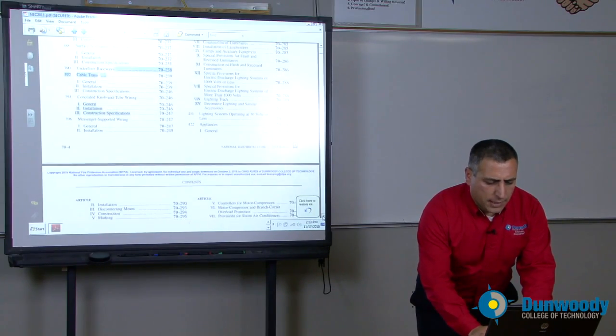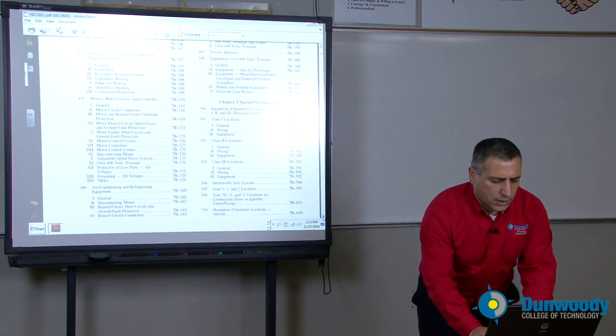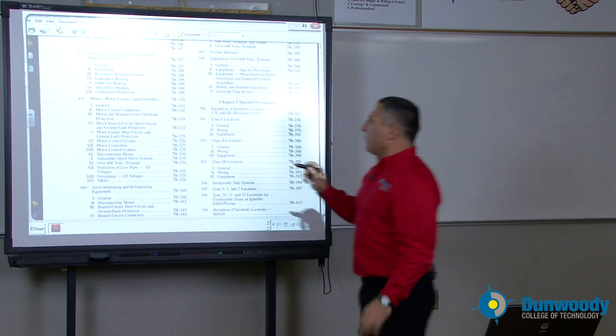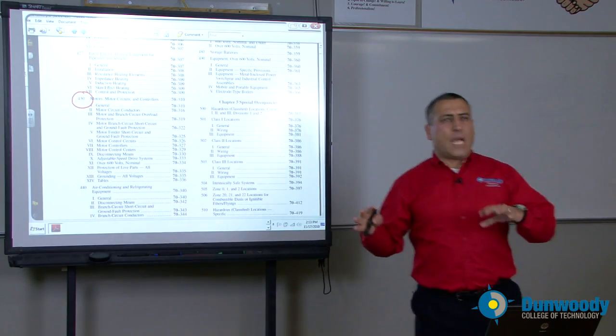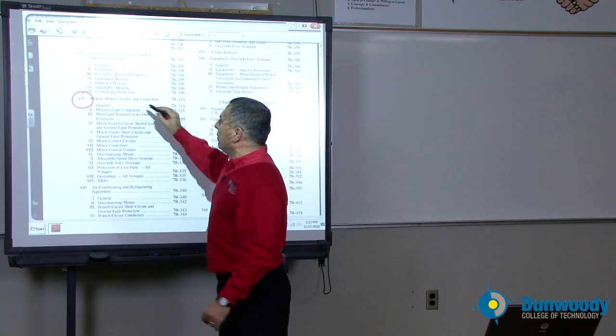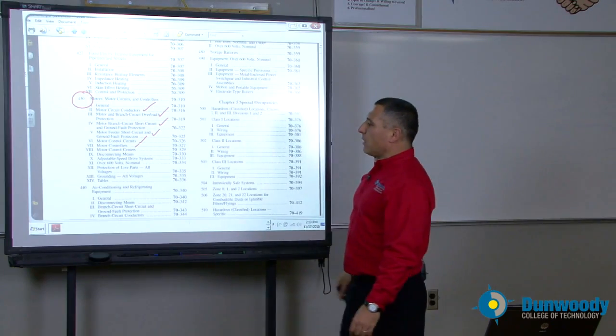Moving on, the most important article I want to highlight is article 430. Every machine that has a motor has to adhere to article 430. How do you size the conductor, the overcurrent protection device, the control circuit, the overload? All this information is found directly in this article — from the motor circuit conductor into the overload, into the branch circuit, the feeder, and the control conductor.